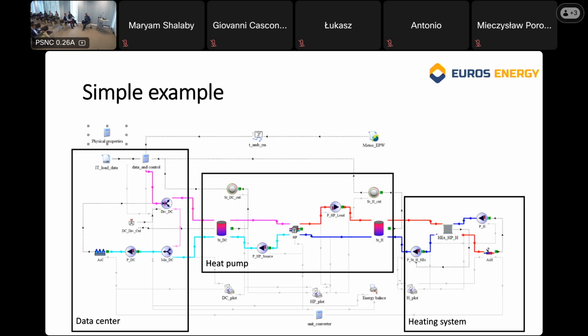And additionally, you can see here an auxiliary cooling device and an auxiliary heating device. It means that if the waste heat utilization from the data center is not enough, if the transfer from the data center to the building is not enough to cool down the data center or heat up the building, we have supporting devices. The idea of this example is to calculate how much electrical energy is needed for the heat pump, and how much additional cooling energy and heating energy we need, besides the work done by the heat pump.